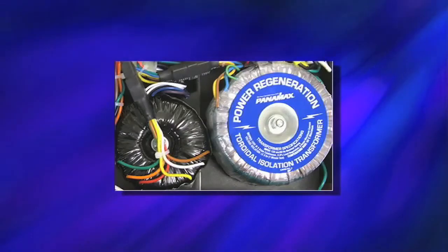Power regeneration is a balanced power technology. Grounded neutral, single-phase power in North America is inherently unbalanced with respect to earth ground. This allows common mode noise to propagate into power supplies and signal references. Power regeneration, as found in some premium power management products, can be used to mitigate this problem.